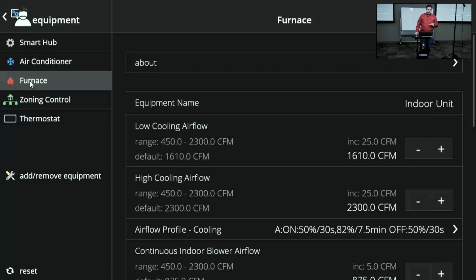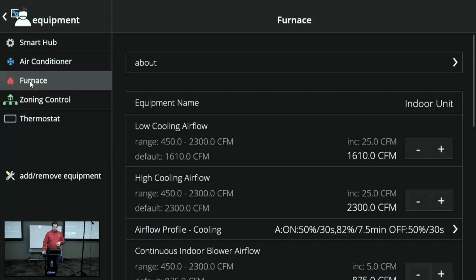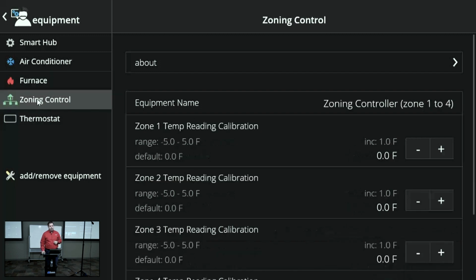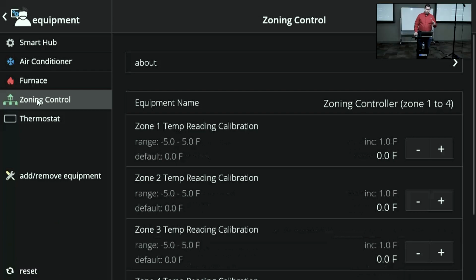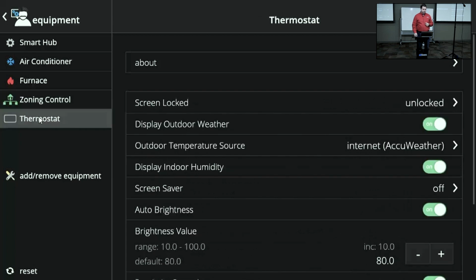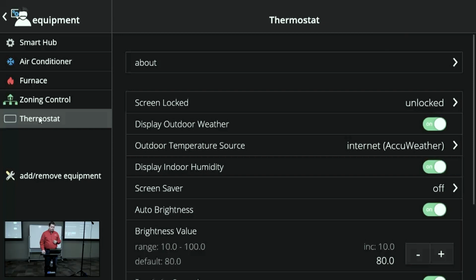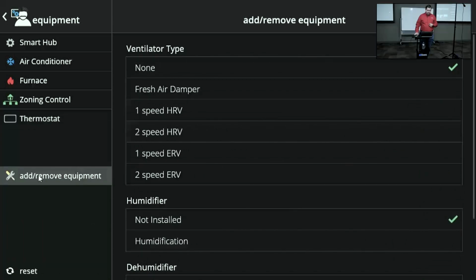In your furnaces, this is where you're going to adjust your low cooling and high cooling airflow. Same thing for your heating CFM. For heat pump systems, you have to go to the heat pump tab to adjust your airflow for some reason that I have not yet understood, but just another little quirk. So in that zone control setting, that's where you adjust mainly your temp calibration. There's, again, not a whole lot that you'll need to adjust in there. The thermostat is, again, just basic display settings, things like that, that typically you don't have to play around with too much. And then the add or remove non-communicating equipment is where we could add in a fresh air damper, HRV, ERV, something like that.